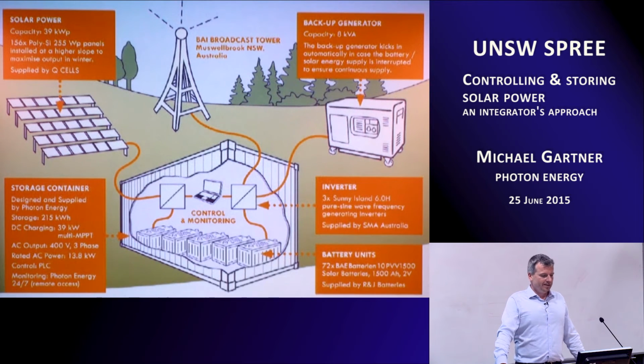When we ran these algorithms, we realised that for this site to have about, it's actually over 90%, about 94% autonomy, we needed about 216 kilowatt hours of battery storage, charged by 39 kilowatts of solar, running a load somewhere in the vicinity of 6 to 7 kilowatts of constant load with slight variability.